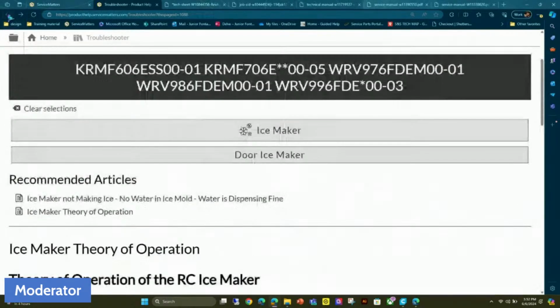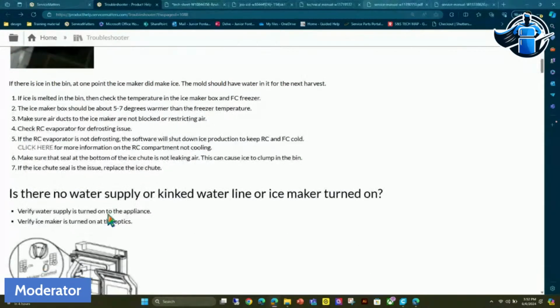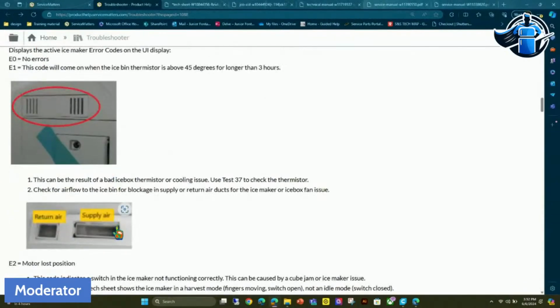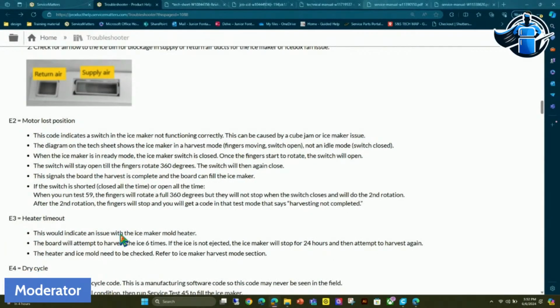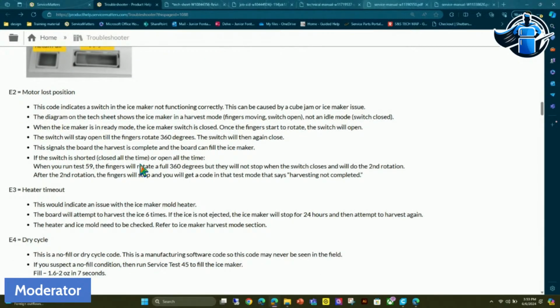Best place to go through the error codes that tell you more of the theory of the error codes is going to be, if you're in the troubleshooter, you'll have to go through the not making ice article, scroll down to where the fault codes are. Again, the tech sheet is not going to give you a description. It's going to give you a very, very bare minimum. It's going to tell you E2 motor loss position. It's not going to give you really the potential causes of a motor loss position. As you can see, this code indicates a switch in the ice maker is not functioning correctly. This can be caused by a cube jam or the ice maker issue. And it breaks down each code individually and what they mean.